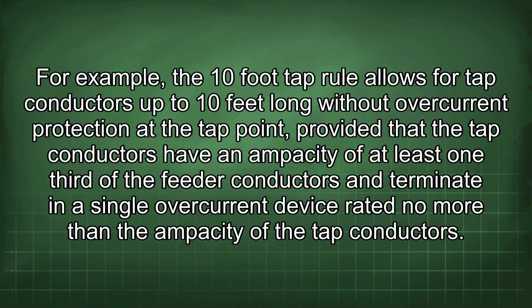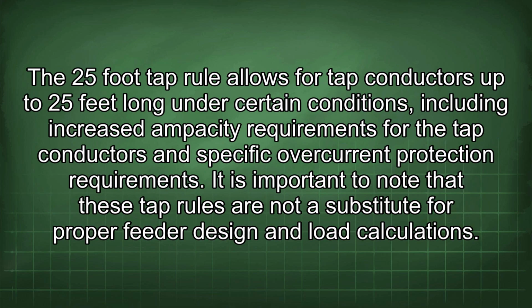For example, the 10-foot tap rule allows for tap conductors up to 10 feet long without overcurrent protection at the tap point, provided that the tap conductors have an ampacity of at least 1/3 of the feeder conductors and terminate in a single overcurrent device rated no more than the ampacity of the tap conductors. The 25-foot tap rule allows for tap conductors up to 25 feet long under certain conditions, including increased ampacity requirements for the tap conductors and specific overcurrent protection requirements.